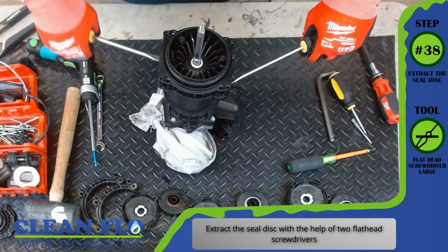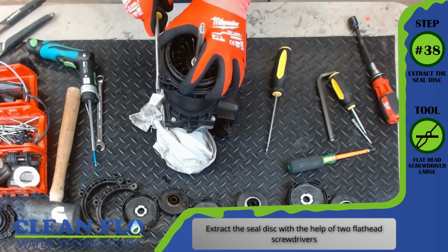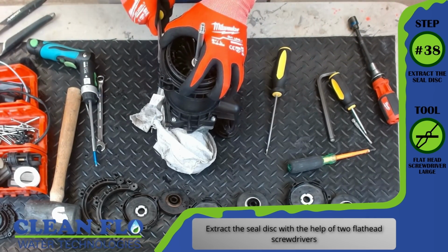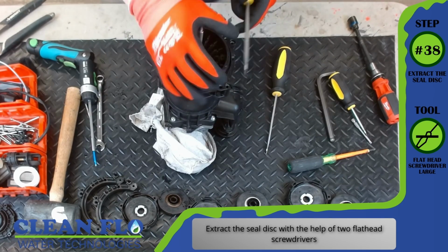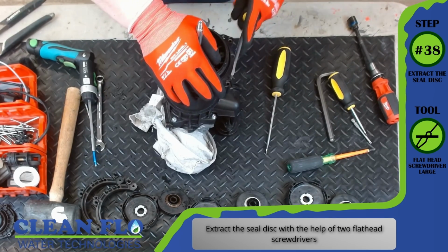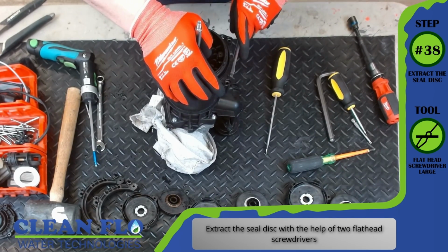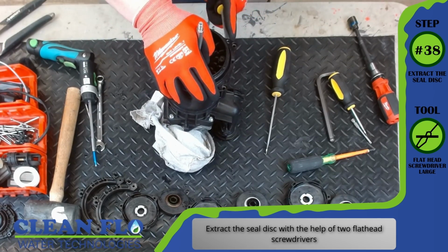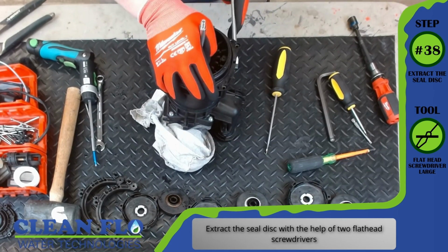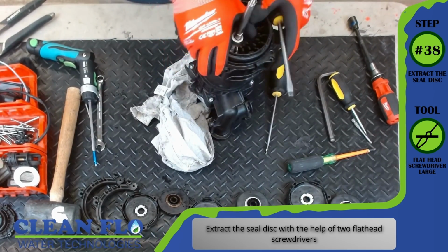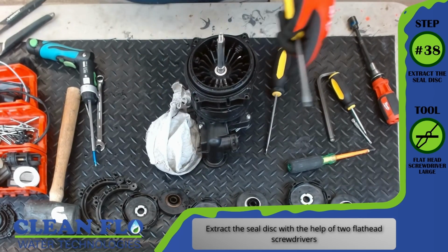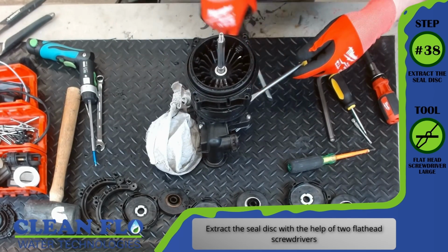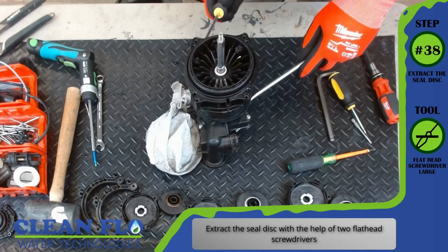Once you have got it slightly pried, you could go back and forth from side to side, slowly loosening the seal disc from the pump body. The seal disc allows the motor to be cooled, as well as providing a location for the mechanical seal to seal the shaft into the motor.